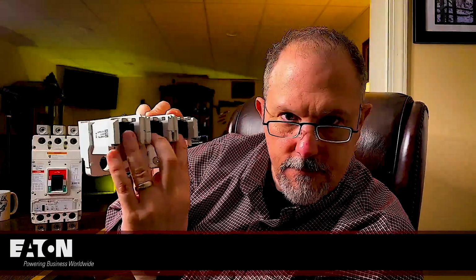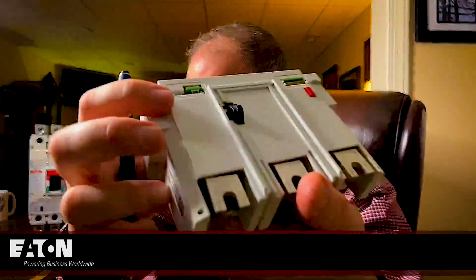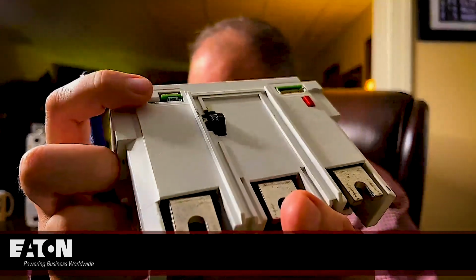My current, this sits in the breaker like this. The current comes through here, goes through these three sensors that are built into the device right here. And then these are the lugs that you put your load conductors on. This is the brain. Inside of here is a microprocessor board. You can almost see the green board right there. So this is the microprocessor, the brain that tells this guy when to trip. And all of that happens right down here on the bottom. There's your load, and these are your line lugs.